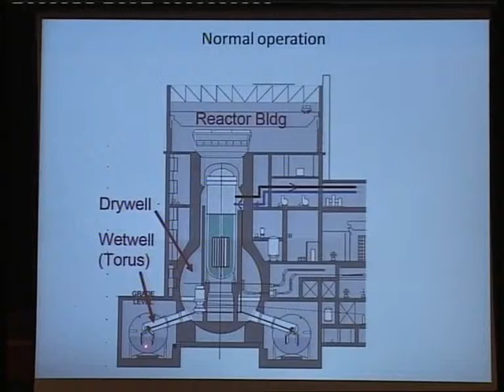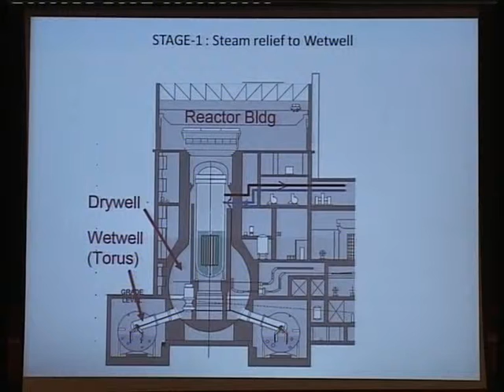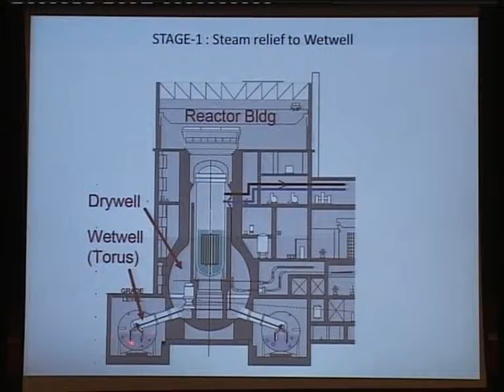In the event there is less water, the water level comes down and the pressure builds up. Then automatically pressure relief valves provided in the circuit relieve the pressure inside this vessel, because we do not want at any cost the reactor vessel to be jeopardized. So the pressure is relieved, but in the process the pressure in this part builds up, and that has to be controlled by cooling here. If the cooling is not there, then you are unable to reduce the pressure.